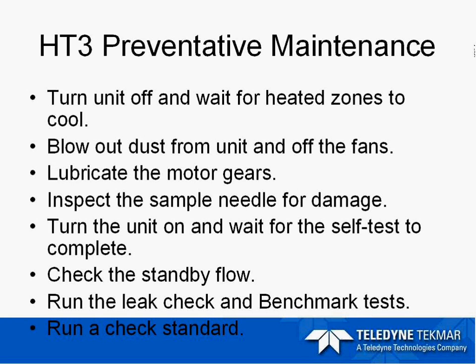Common things to check during preventative maintenance of the HT3: turn the unit off, waiting for the heated zones to cool. Blow all the dust out from the unit, clean off the fans, and make sure all the optical sensors are clean. Lubricate the motor gears. Inspect the sample needle for damage. Allow it to go through self-test. Check for leaks, run a leak check and a benchmark test, and then run your checkout standard.